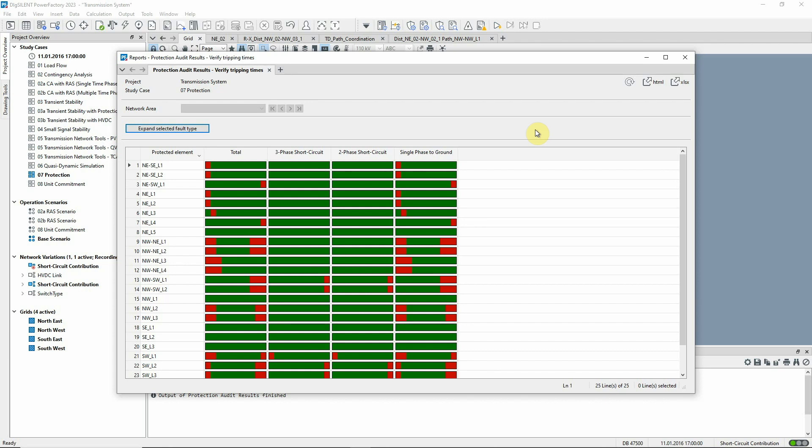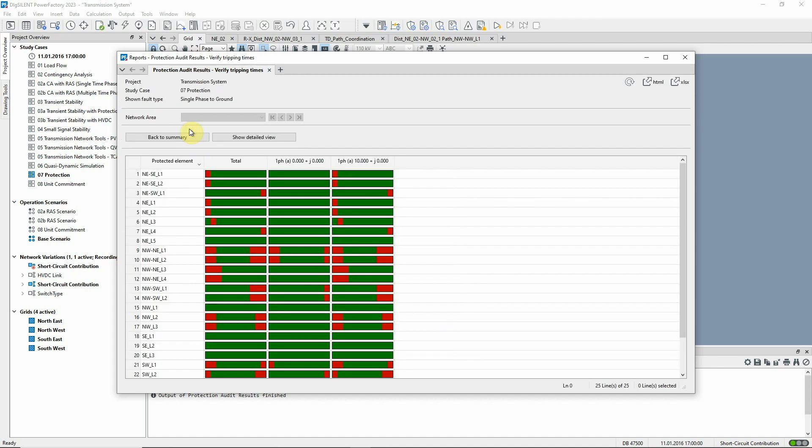As an example, let's take a look at the single phase fault for the line NWL2. After expanding the single phase fault, the single phase faults with and without fault impedance are shown. When considering faults with 10 ohm fault impedance on line NWL2, there are tripping times above 0.5 seconds.